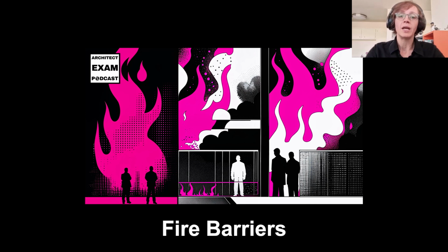Let's take a look at some of the characteristics for a fire barrier. In terms of fire rating, it does have a significantly high fire resistance rating, between 1 and up to 3 hours. We looked at the firewall, it was 2 to 4. So fire barriers are up there as well, between 1 to 3 hour ratings. So let's talk also about vertical continuity. The fire barriers do need to extend from the floor all the way up to the structural deck. They're not structurally independent like a firewall, so they don't need to stand if a building collapses.